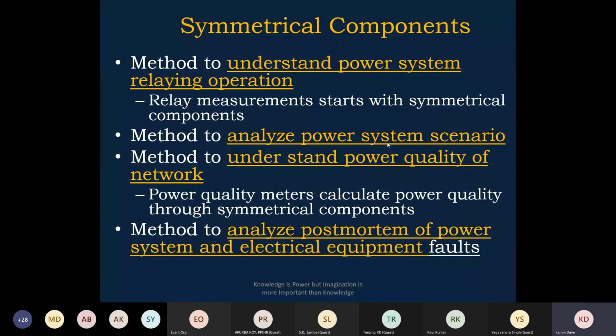It is also a method to analyze the postmortem of power system and electrical equipment faults. When there is a fault in the network or an equipment fault, like a transformer fault, most of the functions work on logic based on interlocks of the symmetrical components. So we try to understand this during post-mortem analysis of power system faults.